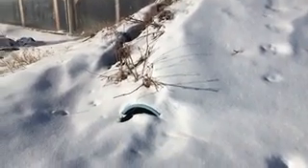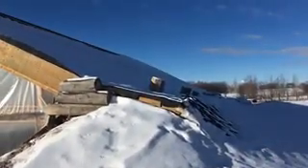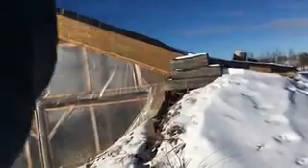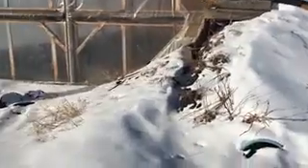In the back of the hill you'll see this tube — this is one of the large drain pipes from the City of Calgary that I got used for just a few dollars each instead of a thousand bucks each, and they run 200 feet. There are two sections. The first section comes in at that end for the air intake because the wind comes from the west. This here is the exhaust, and it's on the bottom. When the exhaust air comes out the bottom it heats up the soil mass around the pipes in the ground. The insulation comes down along here and then down below, so the entire section of earth here is enclosed with insulation. There's actually no insulation between the back wall of the greenhouse and this section, in an effort to transfer even more heat into that area. Sometimes these are known as a camel nose, or in conventional terms it's a large do-it-yourself heat recovery ventilator.